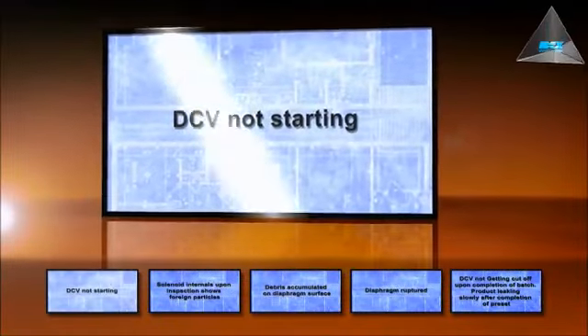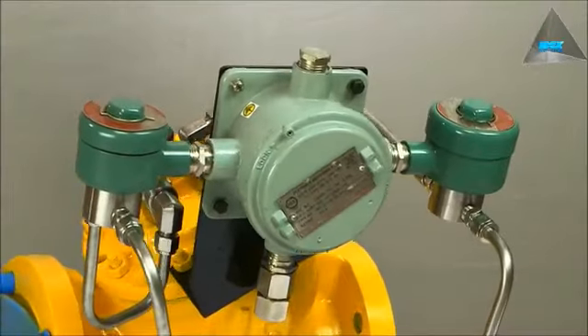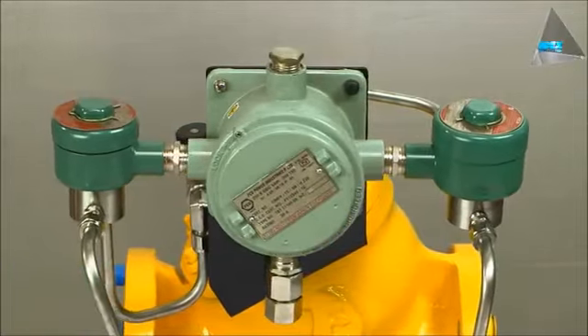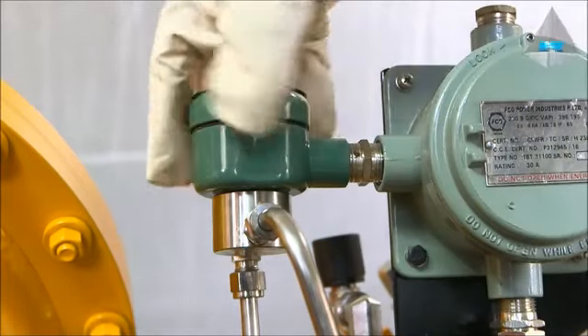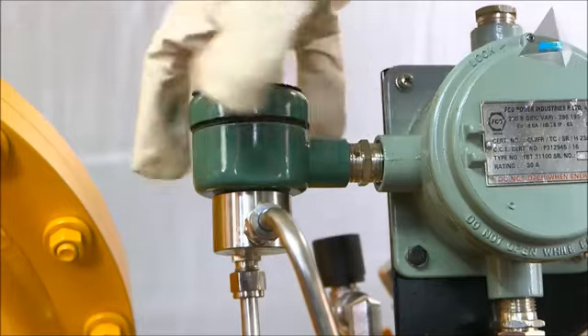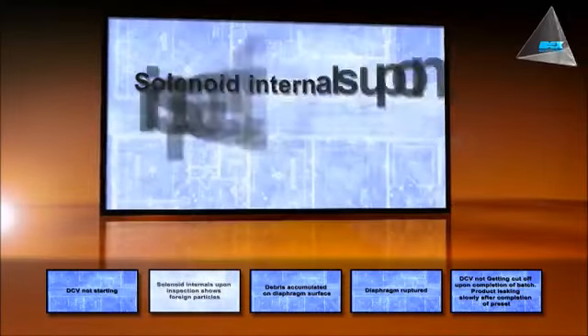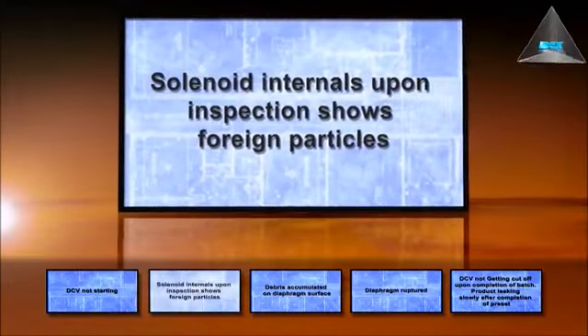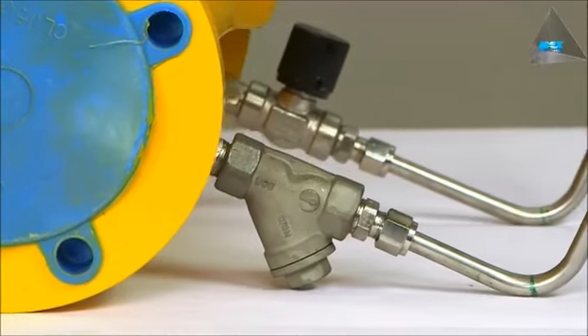DCV not starting. Possible cause: valve solenoids not responding. Solution: check solenoid functionality. Replace the coil and solenoid if functionality is not appropriate. Solenoid internals upon inspection show foreign particles. Solution: clean the internals and clean the strainer basket.